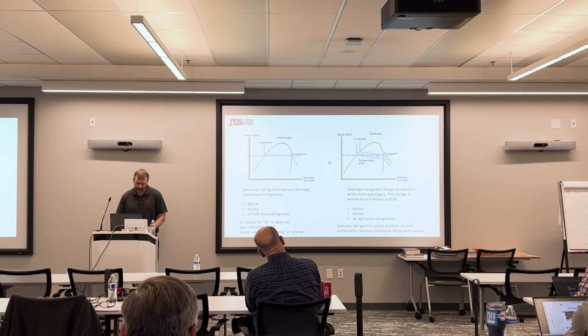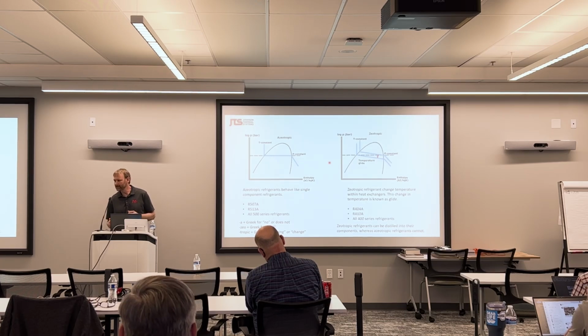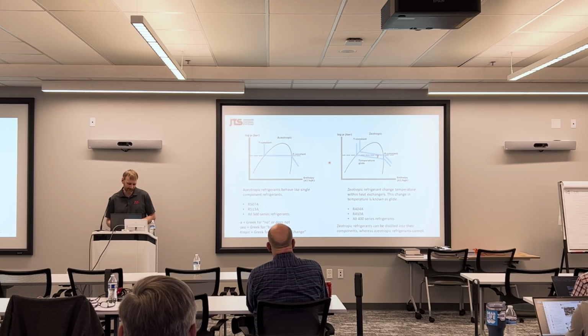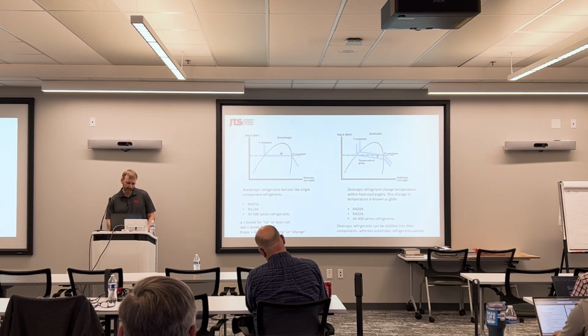All right, so we're here to talk about glide. Basically, there are two types of blended refrigerant. There's what we call an azeotrope, or I've heard it pronounced a few ways: azeotrope, azeotropic. I'm not 100% sure which is right, but azeotropic refrigerants include R507, R513A, and any R500 series refrigerant. These are blends that behave like a single component. So as you move across the pressure enthalpy diagram, you've got a constant temperature at constant pressure. The term azeotropic is actually Greek in origin. A is Greek for no, zeo is Greek for boil, and tropic is Greek for turning or change. Therefore, an azeotropic is a refrigerant that does not change temperature as it boils.